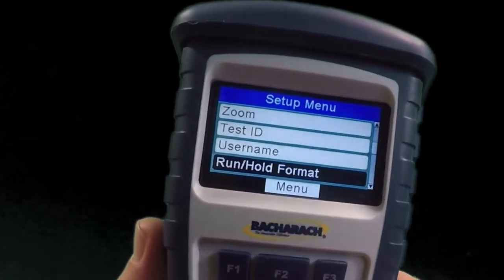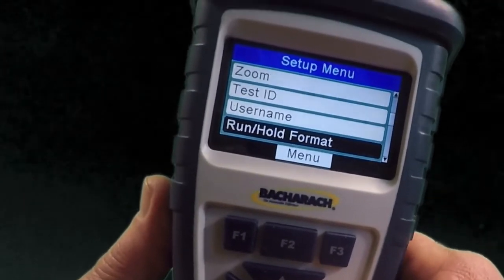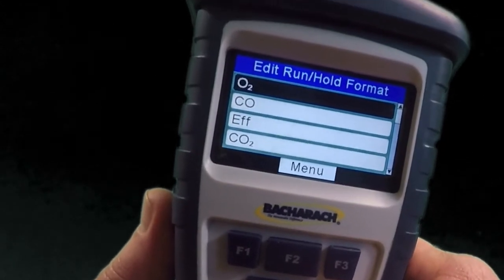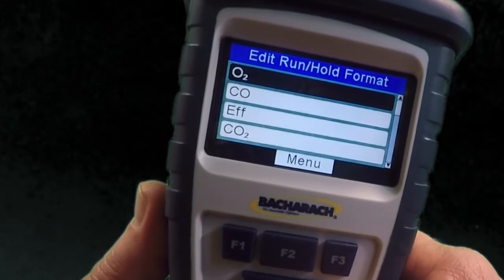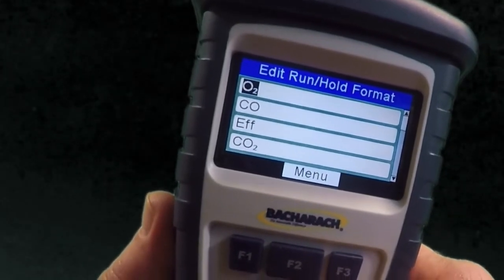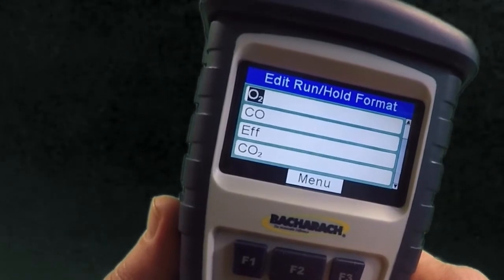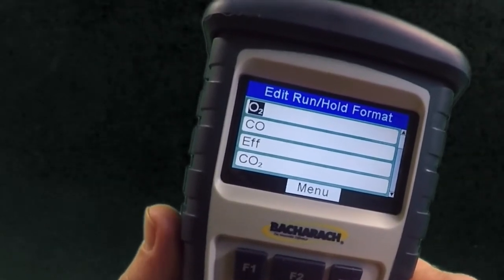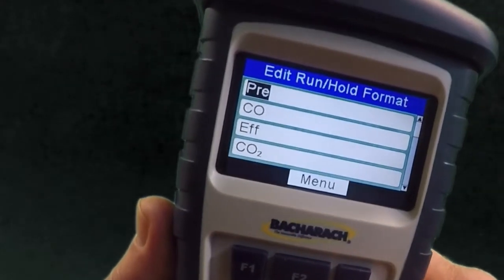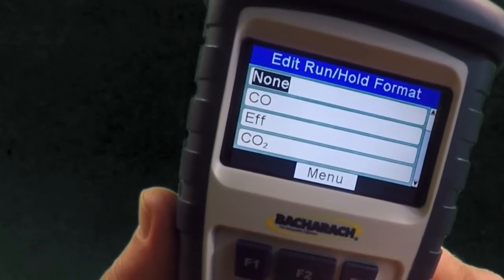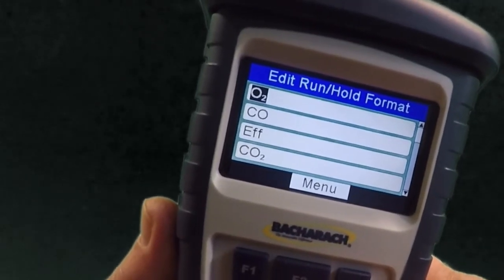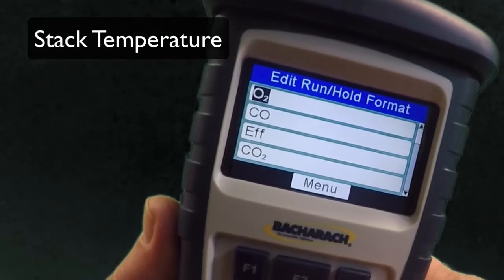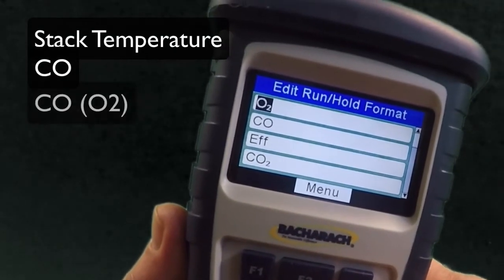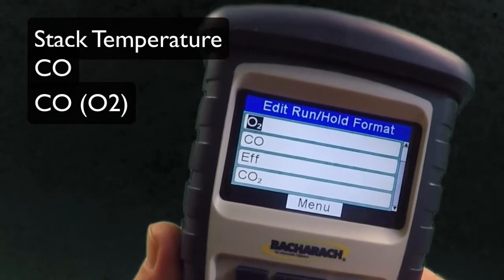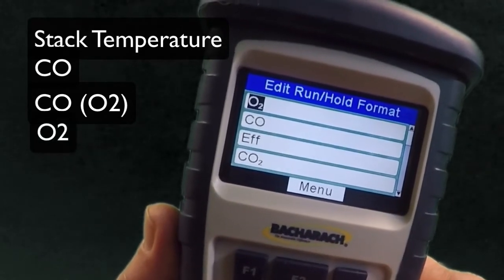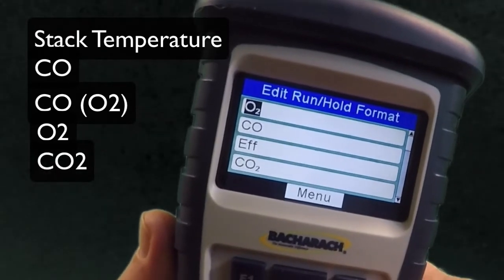The run-hold format allows you to customize the display. We'll select that. You hit Edit Format. When you press the Enter button, you'll see it highlights the line, or the number, that you want to change, the parameter you want to change, and then we can scroll up or down to select whatever parameter you want. We'll talk more about that later, but consider including the stack temperature, the diluted carbon monoxide reading, the carbon monoxide reference to a 0% oxygen or the CO air free reading, the oxygen reading, that's pretty important, the carbon dioxide reading, and the steady state efficiency reading.